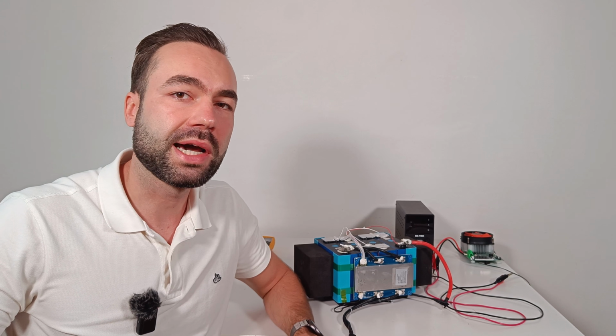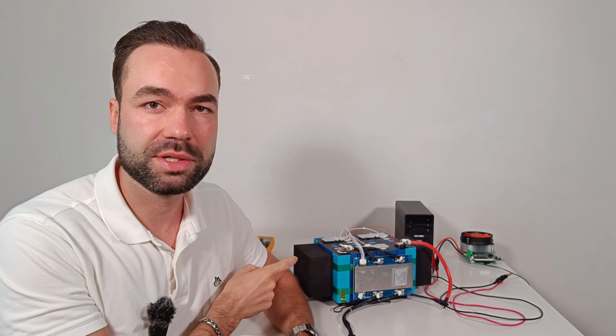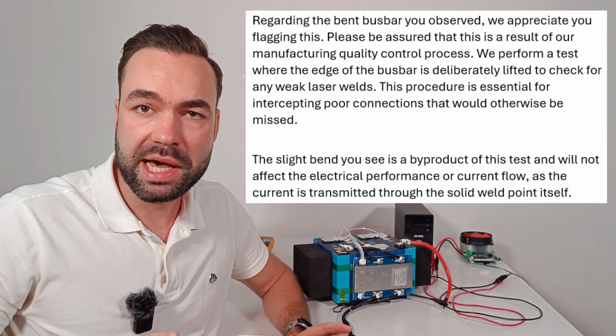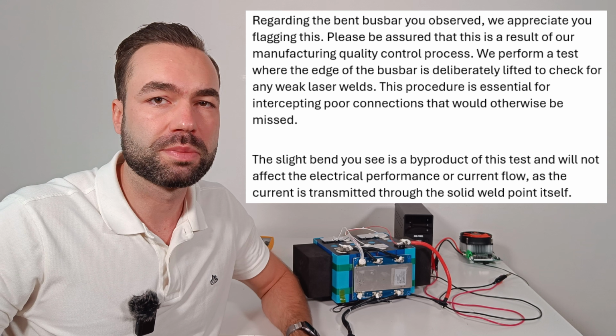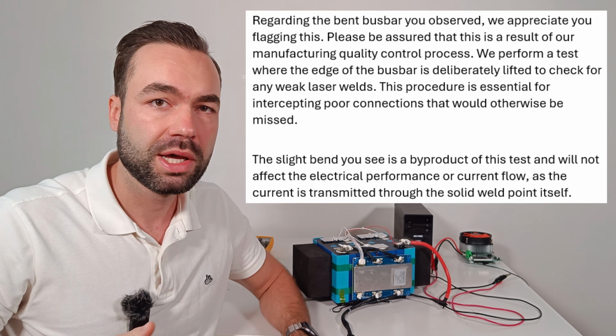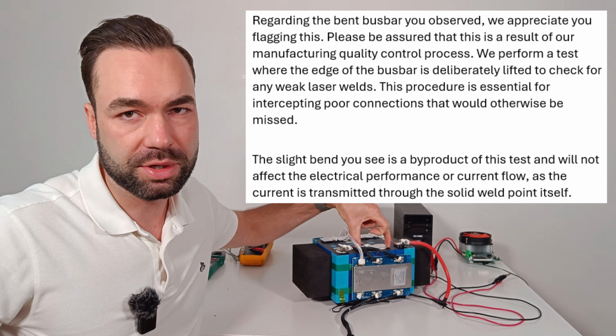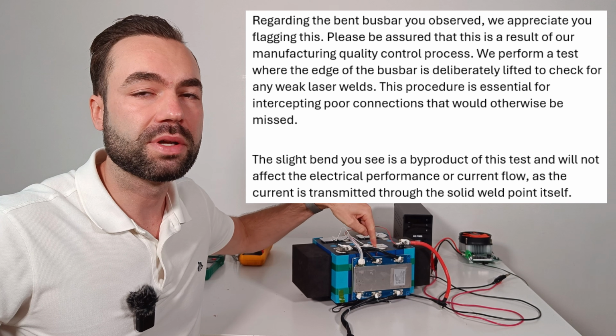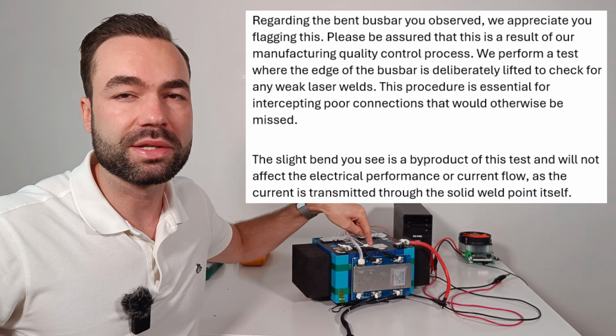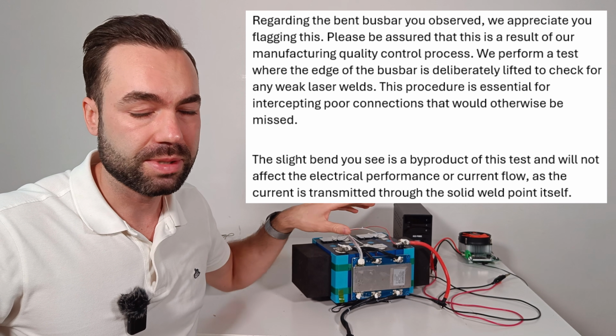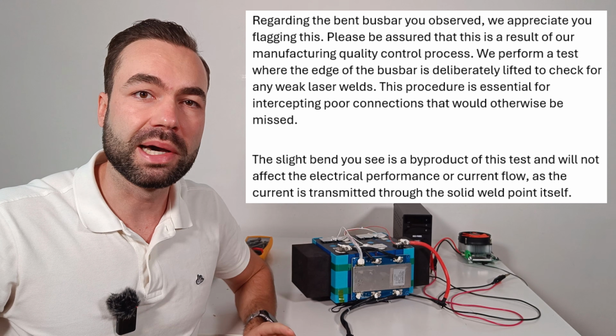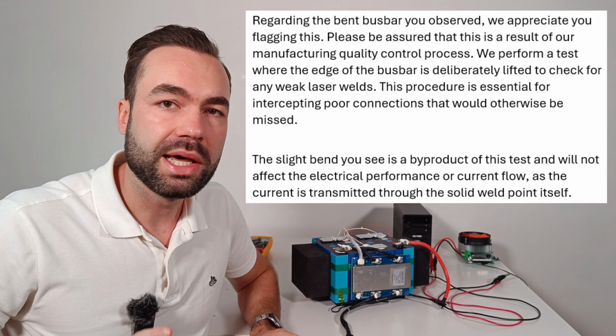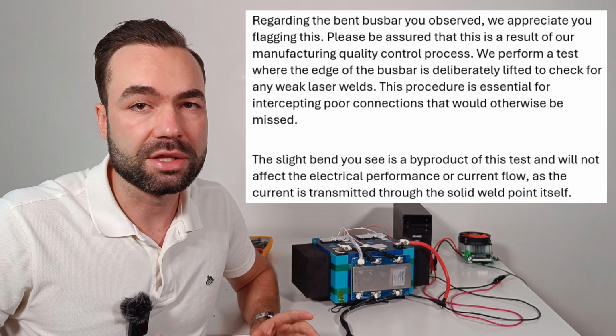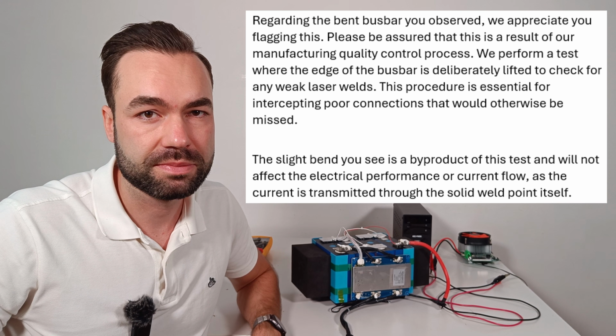I followed up with Dyness about the bent bus bars. They explained that this is actually part of their quality control process. During production, they lift the edge of the bus bars to test the strength of the laser welds. If the weld isn't solid, it will break during this test. So while the bend may look concerning, it's a byproduct of testing and doesn't affect performance.